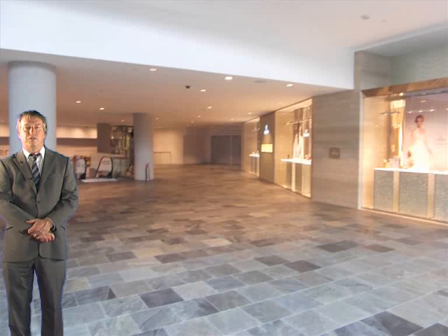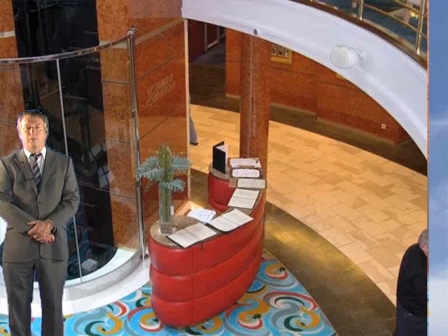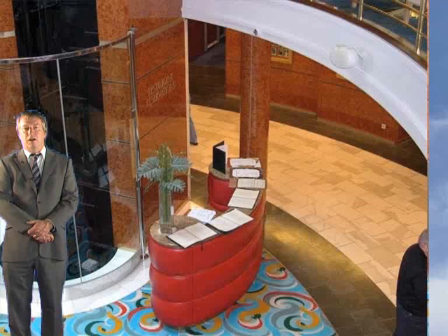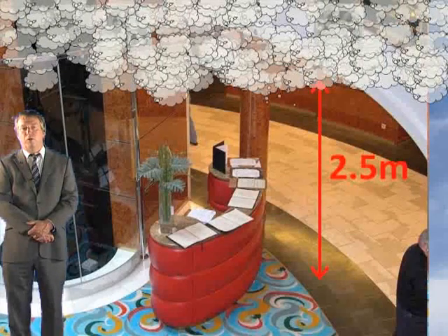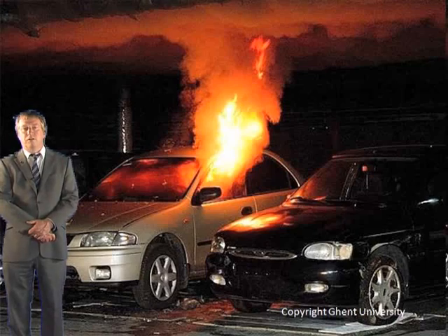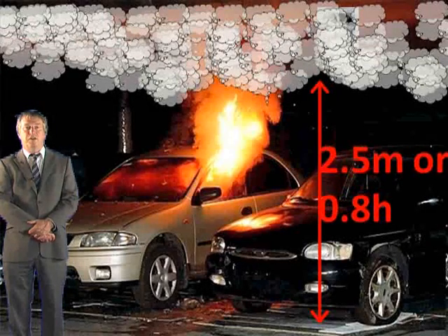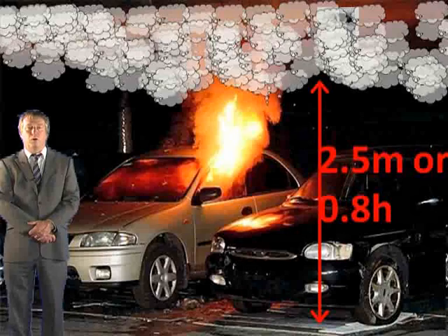Early in the design stage of the building, the designer needs to decide where the base of the smoke layer can safely descend to, or how rapidly it can descend. This decision is guided by a number of parameters that have to be observed. The minimum clear layer height for various buildings for life safety is as follows. Public buildings, for example single-storey malls, exhibition halls, etc., 3 metres. Non-public buildings, for example offices, apartments, factories, open hall type prisons and such like, 2.5 metres. Car parks, 2.5 metres or 80% of the height of the space, whichever is the smaller.